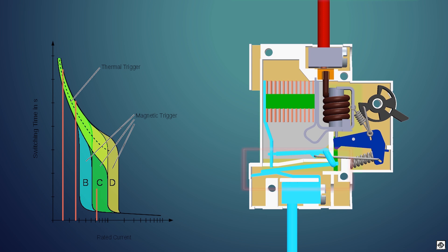So why do we need this solenoid trigger, as the bimetallic strip may protect in a short circuit? Because the bimetallic strip takes time to heat up and expand, and during a short circuit, time is very important. A short circuit needs to stop as soon as possible, hence we have the solenoid to trip the MCB instantly.